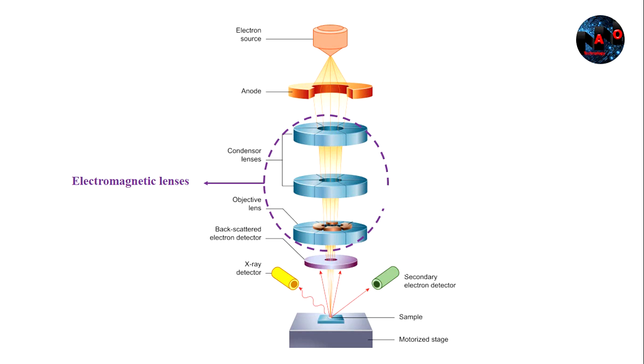Electromagnetic lenses, which are composed of condenser lenses and objective lens, are used to focus the electrons into a beam, adjust beam astigmatism, move the beam across the specimen, and to scan the beam to generate images.